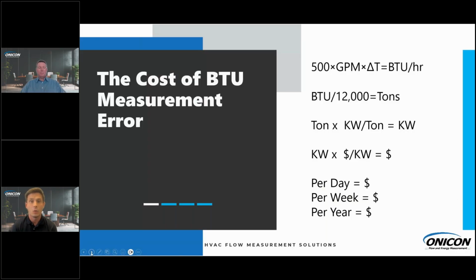With ONICON, we actually reference the specific heat calculation table for that 500. So we're not using that 500, we're actually using the true value, minimizing error. And when we calculate this, we get the BTUs per hour. Then from there, we convert it to tons and then to kilowatts. And then from kilowatts, we can calculate to dollars. So we can see your cost and error per day, per week, all the way to per year.